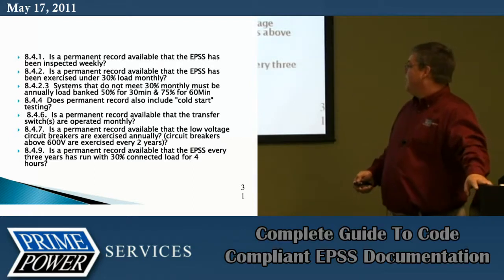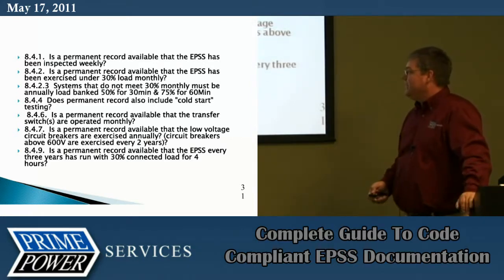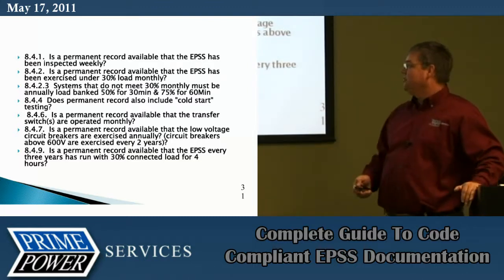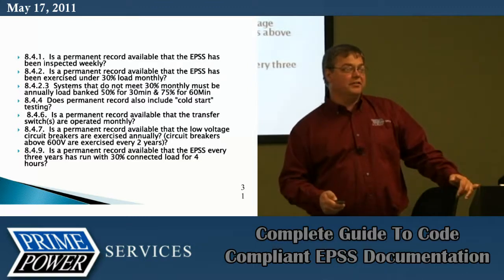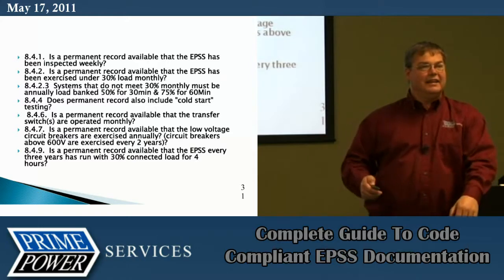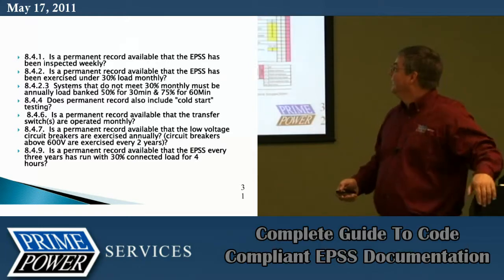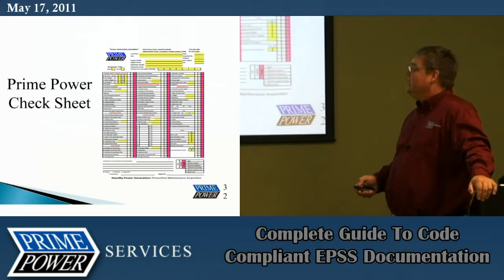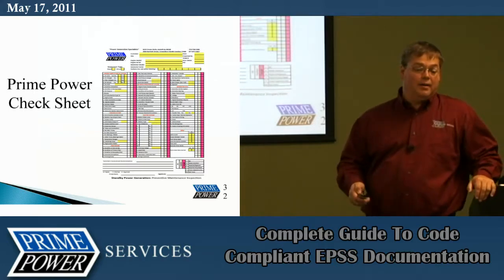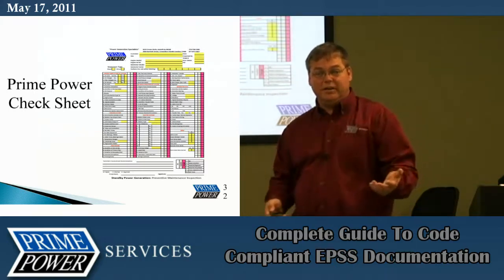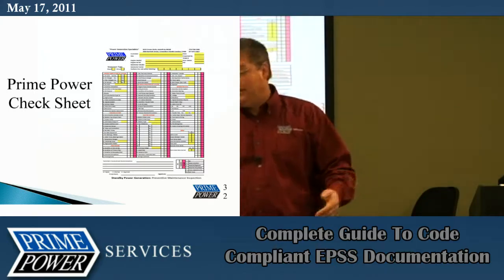All right. Is a permanent record available that EPSS every 3 years has run with 30% connected load for 4 hours? There's your 4-hour, 36-month test. Time, man? Here's our check sheet that I was referring to. That's the one that Prime Power uses. It's on the presentation. You guys probably have it already.